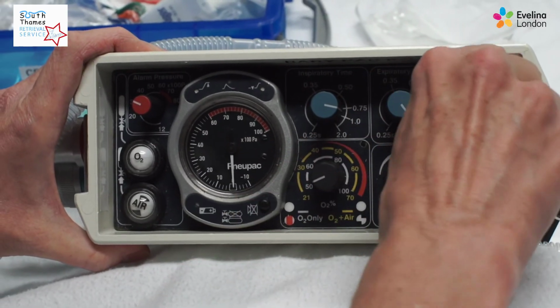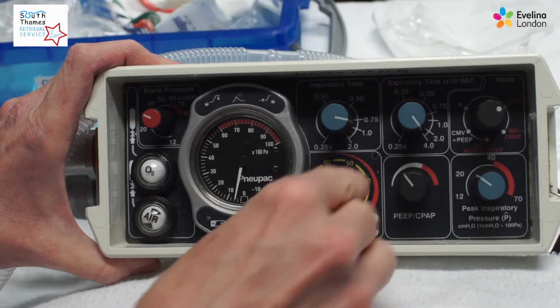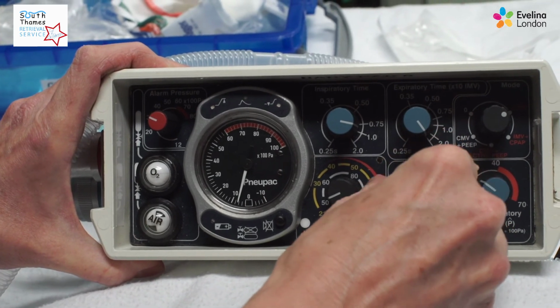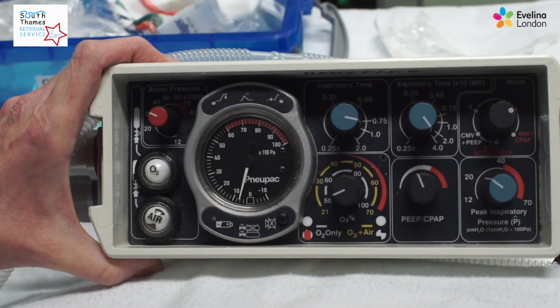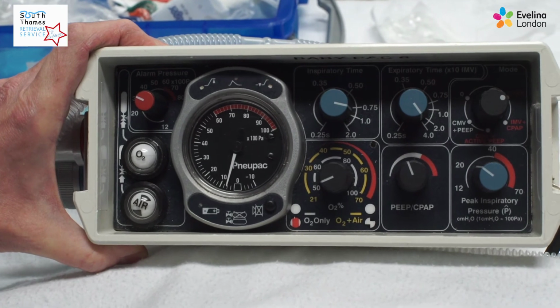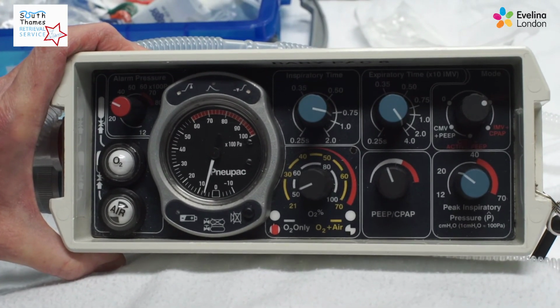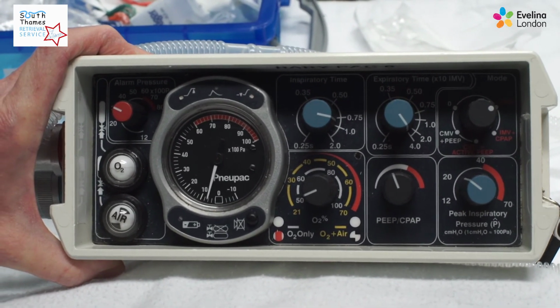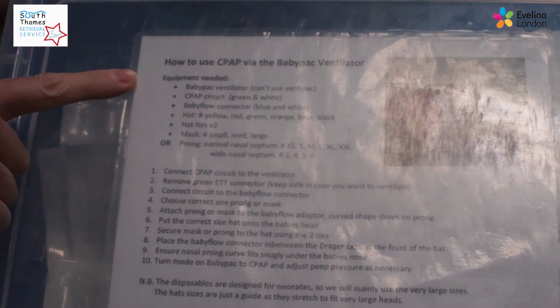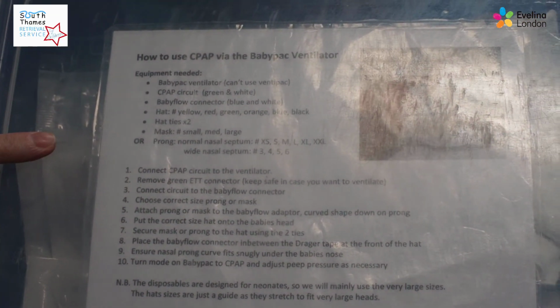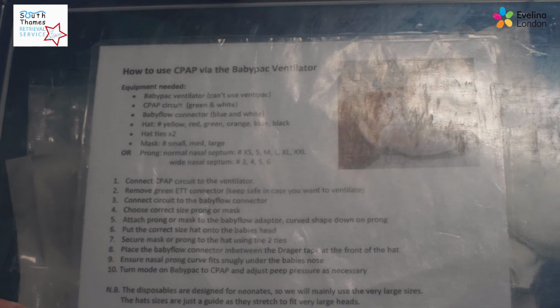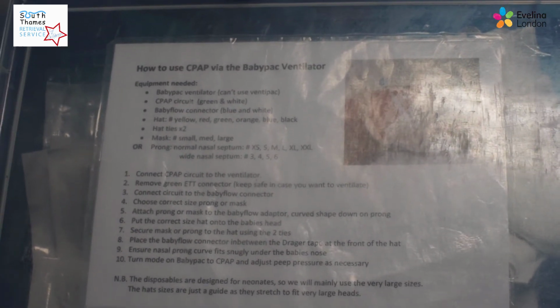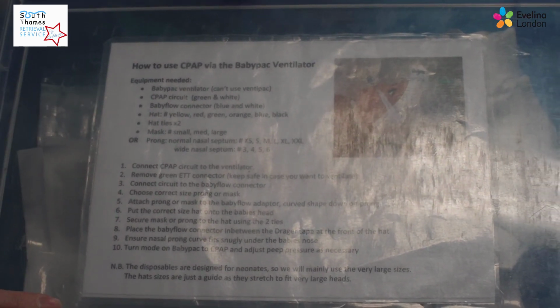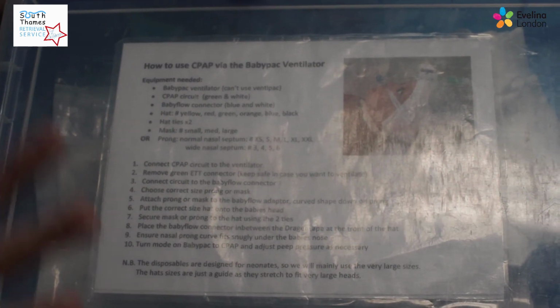To set the CPAP, turn the dial to CPAP and then adjust the pressure as you would like according to the child's needs. So this child now is receiving PEEP of about 5 and seems to be very settled on that. Everything you need to set up CPAP on the Babypac ventilator is in the cupboard in the retrieval room, and there are also packs stored in the ambulance should you need one when you're out, and they contain all the tubing and all the extra bits you need to safely assemble and deliver CPAP.